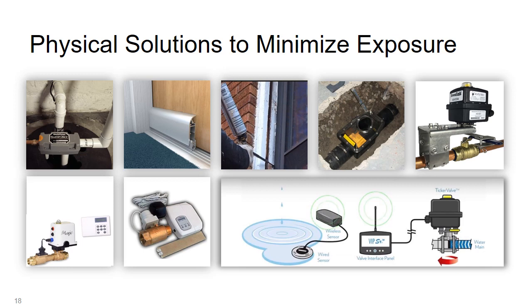Backflow preventers, this would be on the water lines leaving the facility. We want to make sure that in the event of a heavy rainfall or other city upset condition, that we don't have any dirty water coming back into the facility and causing issues through floor drains. The last item on the top row there is a motor-operated control valve, which can remotely control the position of the valve, shutting off water if needed. And then on the bottom, we have inline flow controller modules. And then at the bottom right, a leak detector, which remotely ties into a valve interface panel, so you can shut off the supply of water if there's too much in a given area.